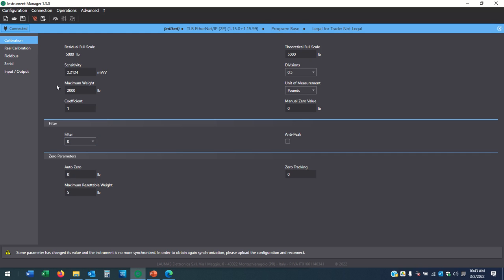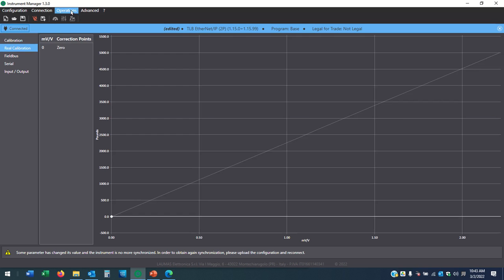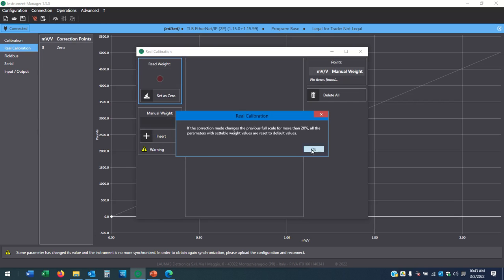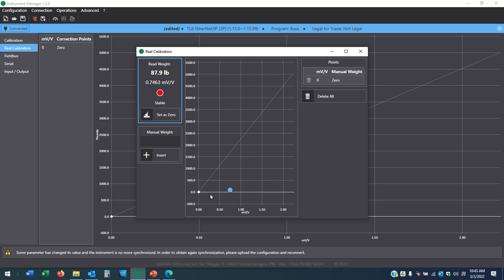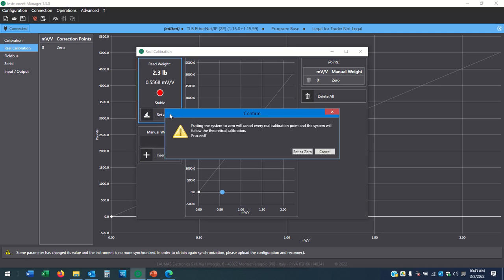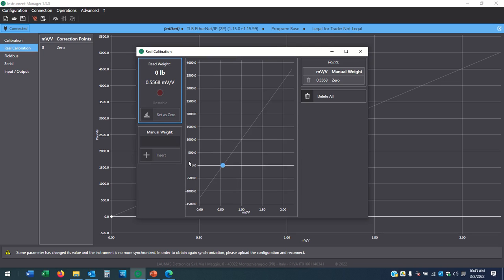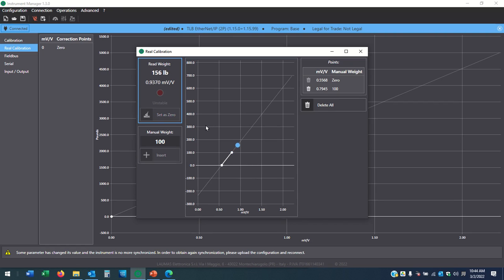Pretty basic. If I do a real calibration, I go to my operations and do a real calibration. Then I can put this at 0, and I'll set that as 0. So the first thing I'm going to do is set that at 0. Then I'm going to put a known weight on it, and let's say my known weight is roughly 100 pounds, but I'm reading 107. I can say that's 100, and boom, it's going to get that point right there. Now I can put some more weight on it, say 300 pounds, and my 300 pounds, however, reads as 303. So I can say this is 300, and boom, it's going to be this.